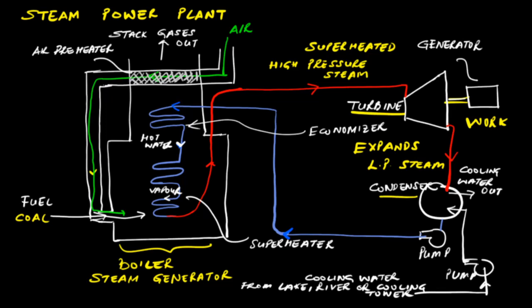In the condenser, heat is transferred from the steam that has exited the turbine to cooling water, causing the steam to condense. Steam power plants need a lot of cooling water and are therefore often located near lakes or rivers. Sometimes, a cooling tower is used where part of the condenser cooling water is evaporated to recover some water for cooling purposes.